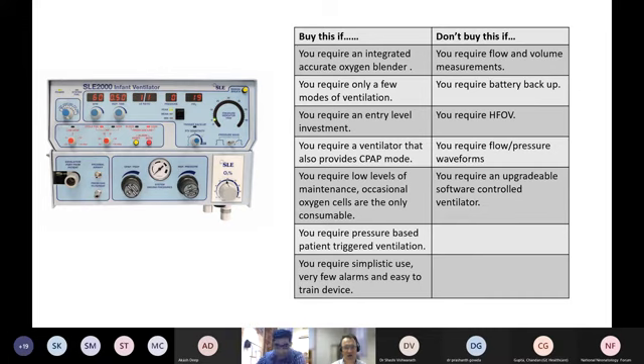Maintenance costs are very low on this kind of ventilator because the only thing that occasionally needs changing is the oxygen cell, which measures the oxygen concentration. There are no other single-use consumables per se. However, if you're looking for something more technologically advanced, such as high-frequency oscillation or a considerable battery backup or flow and volume measurements, then the 2000's not the ventilator for you. You need to start looking at greater steps in technology to be able to deliver those kind of things.